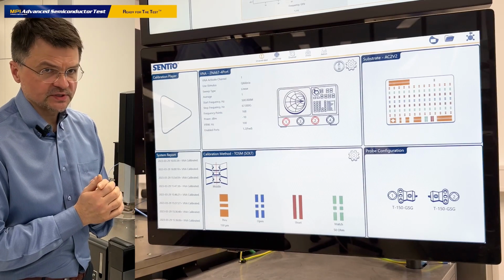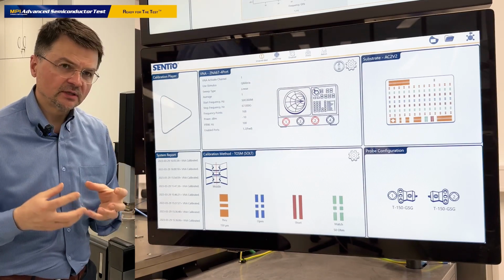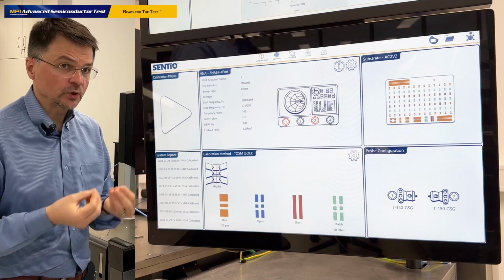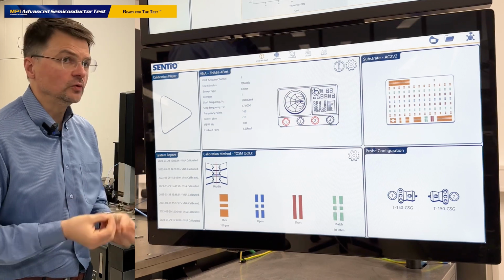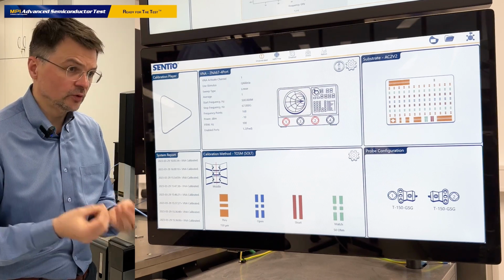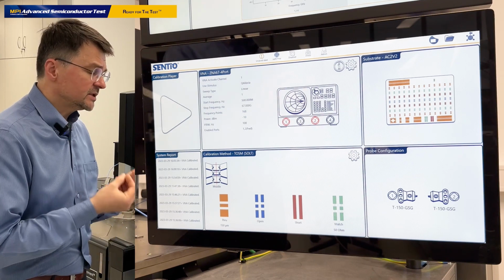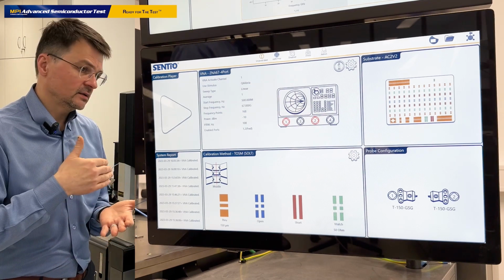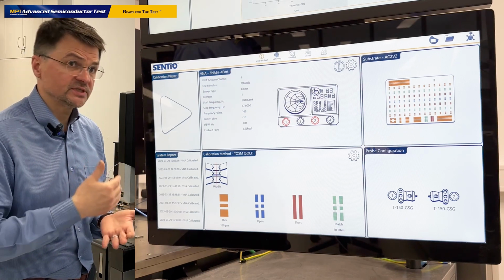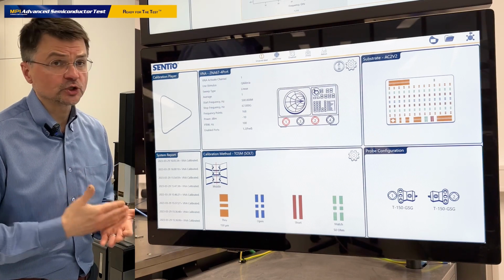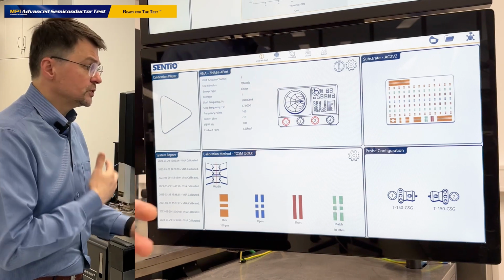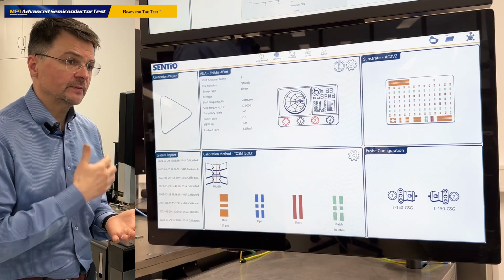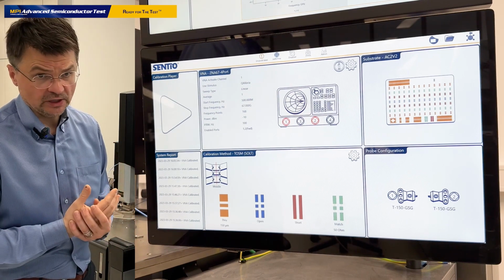When we calibrate our system, we measure electrical reference elements, we call them calibration standards, with known electrical models, with known electrical characteristics. These characteristics are usually described by lumped elements like capacitances, inductances, or resistances associated with the open, short, and load standard. And we also use some modeling approaches to describe losses and delays in our transmission lines.